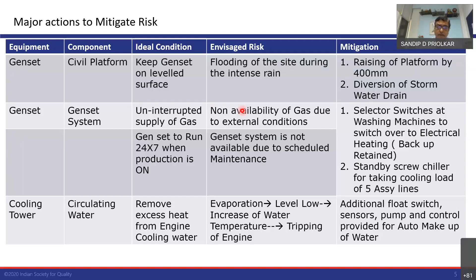Similarly, for the cooling tower, since the system is very critical to the cooling water temperature, we have put additional float switches and sensors so that water availability to the cooling tower is 100%.